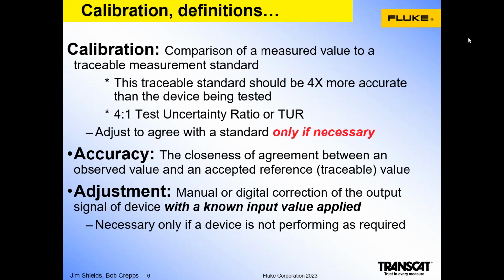Many technicians, or organizations rather, would have the technician make an adjustment on a device if it is greater than 50% of the allowable deviation or specification in error. Whereas if the error of the measured milliamp signal value, for example, is less than 50%, they would suggest that you don't make the adjustment. And again, there's not really a standard that defines when and where you adjust. That's typically a corporate standard or corporate practice, depending on the organization.